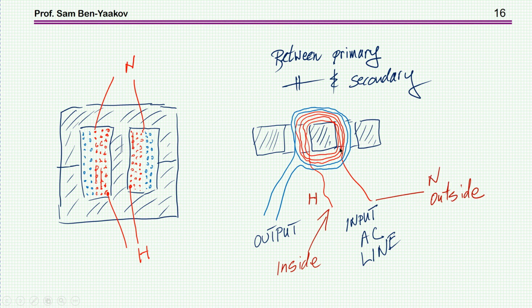So now you have a capacitance, but it's between the neutral and the secondary. Here we see it - this is the neutral side, and the hot side is buried inside. So we have capacitance between the neutral and the output, and therefore there's practically no potential difference - the voltage is very low, so the current will be low.